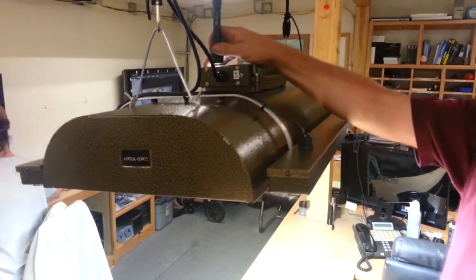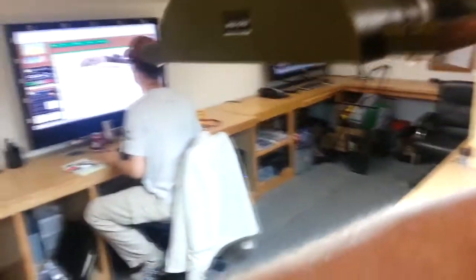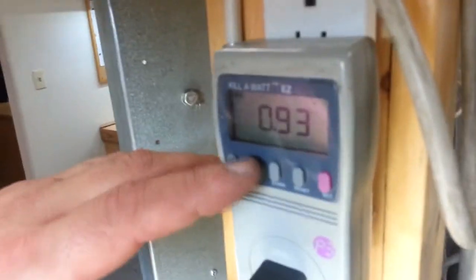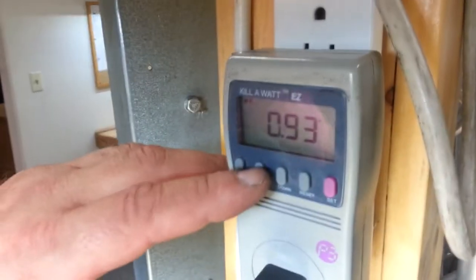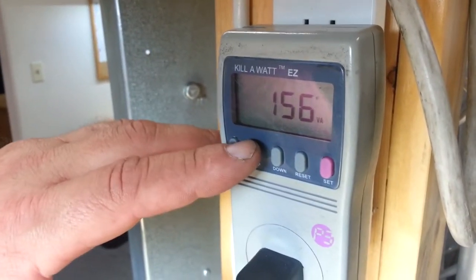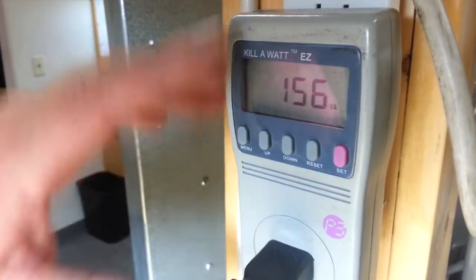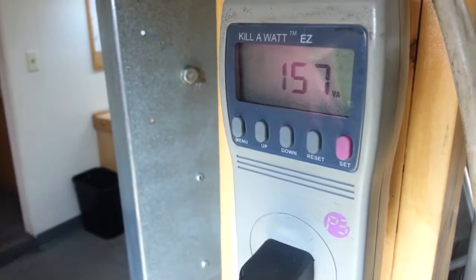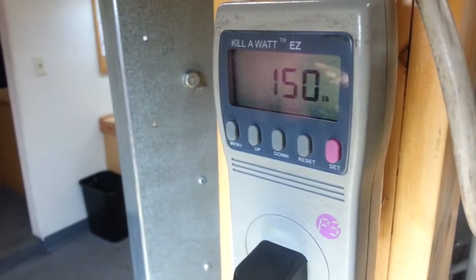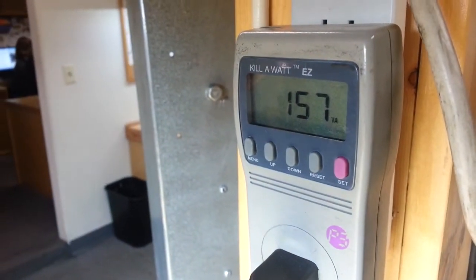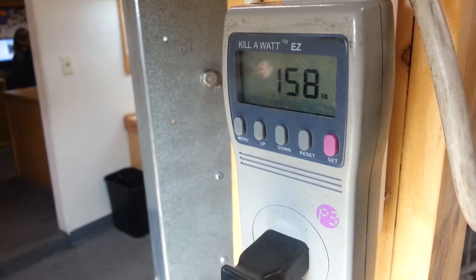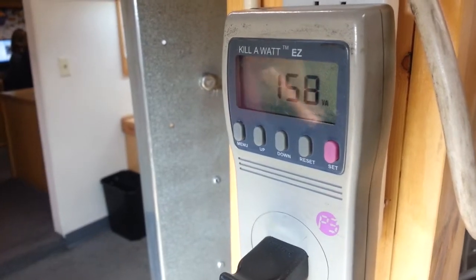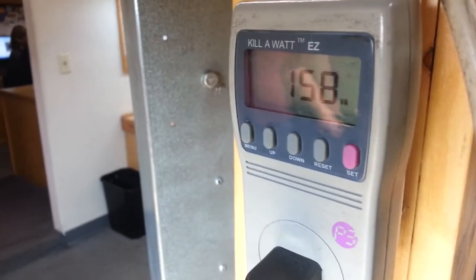But this just knocked my connected loads down. I'll show you on my watt meter here. You can go around. Say we're going 114 volts, 113, 0.93 power factor, 60 hertz, and we're in 156 watts. Now the wattage is going to go up as it warms up. So it just started. It's going to be relatively low. That's going to come up to over 400 watts as it runs.